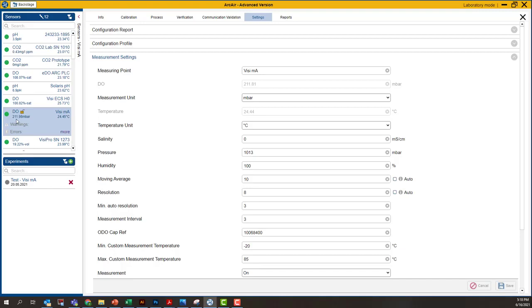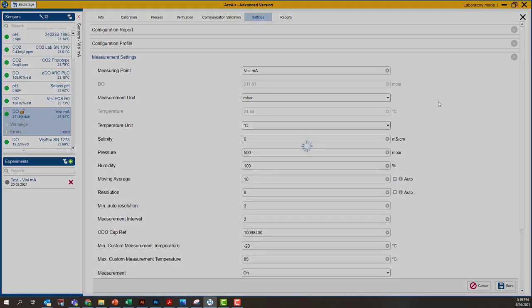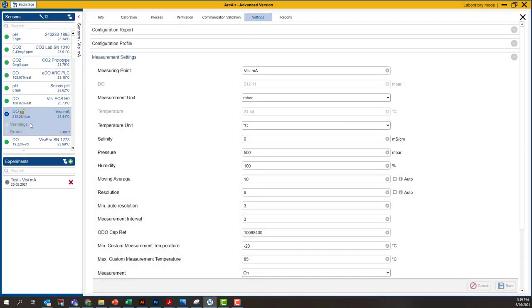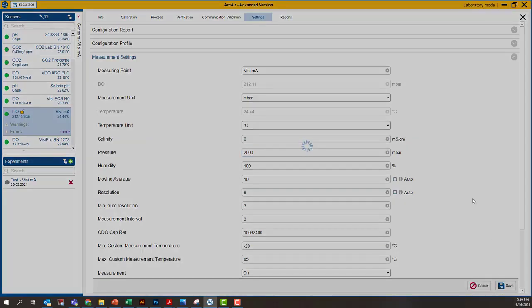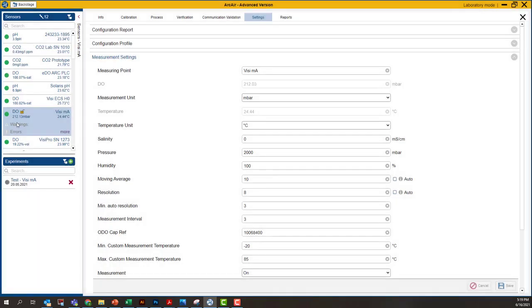And let's perform that same trick. Let's take my measurement and cut it in half. And let's see what happens. And what I can see here is that my actual DO reading did not change at all, no matter what I do to the partial pressure. So I can take and double this as well. Let's say 2000. And I really get no fluctuation in my measurement.